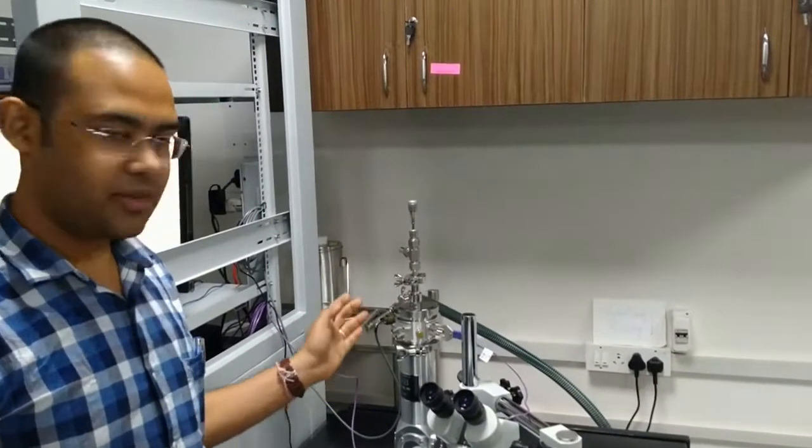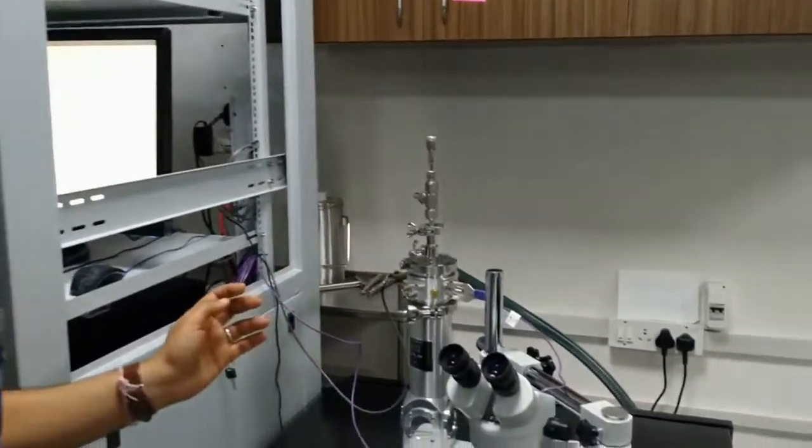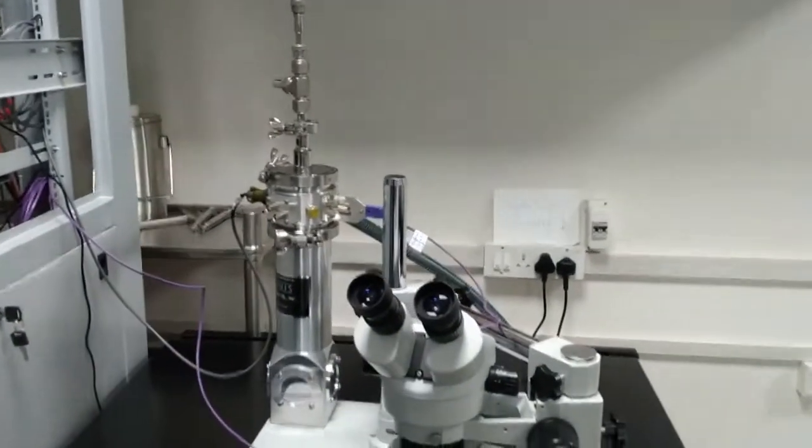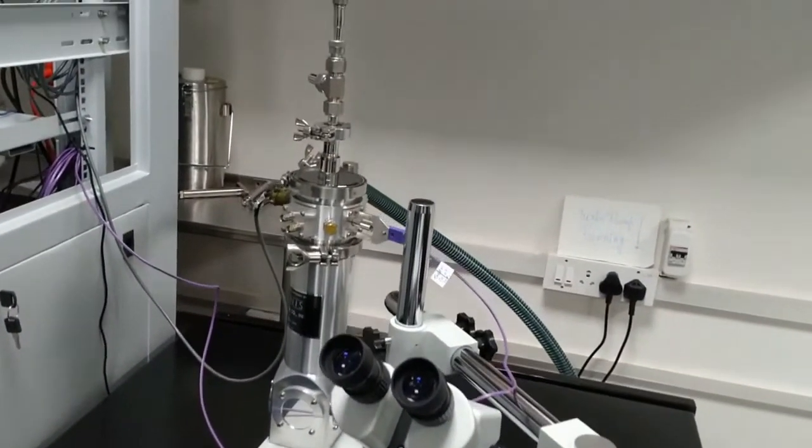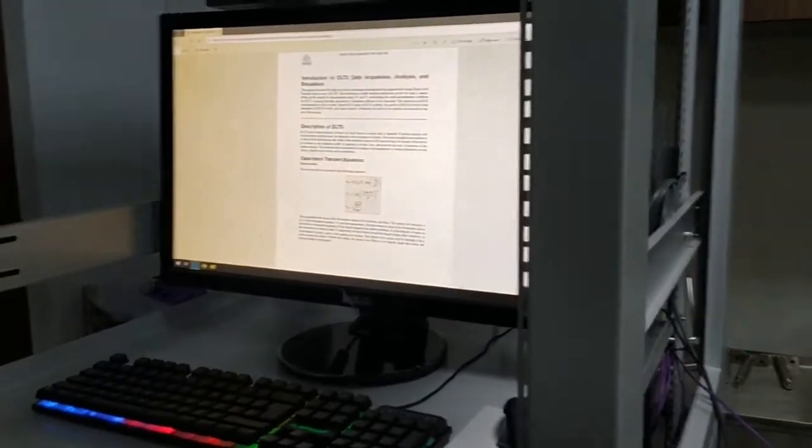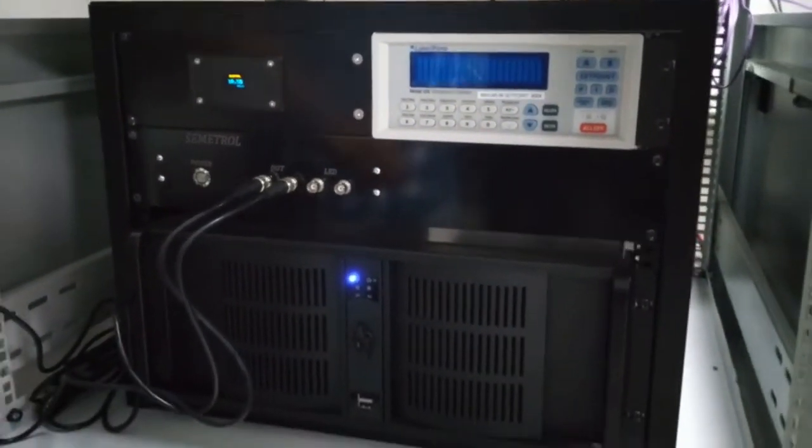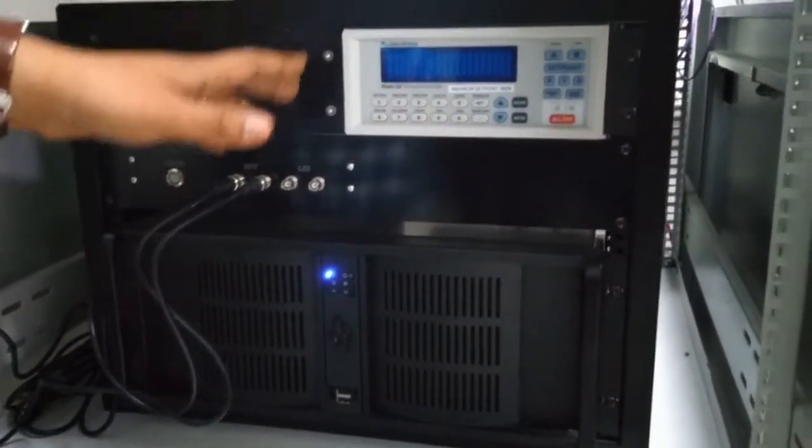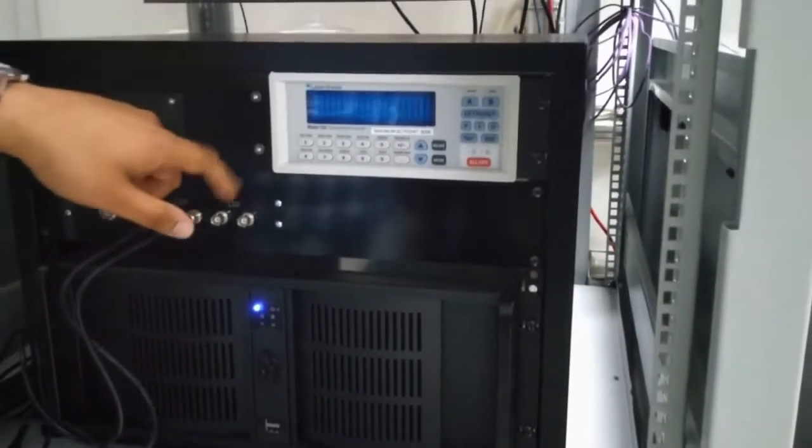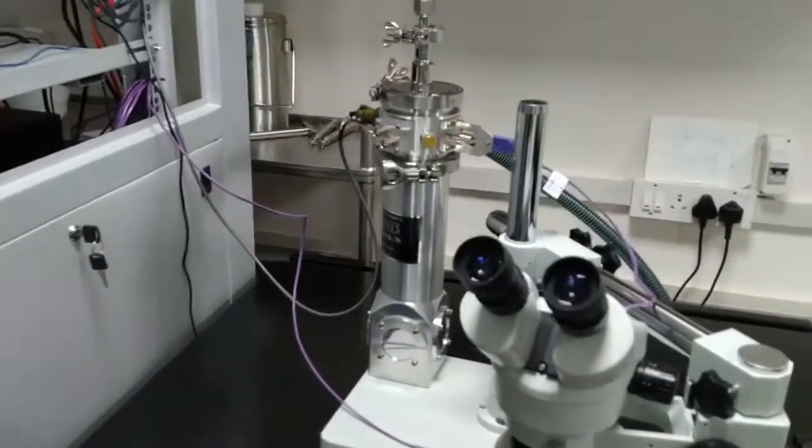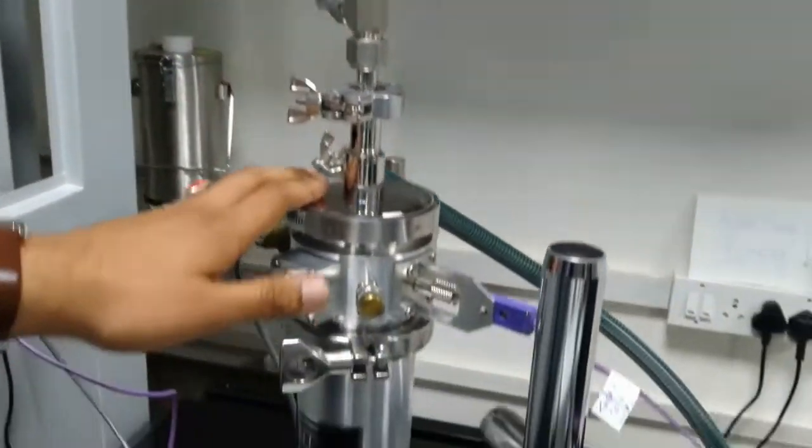This is the deep level transient spectroscopy system which is used to identify energetically deep traps which can be present in trace amounts in our semiconductors, otherwise not detected using normal IV-CV measurements. The trap detection is carried out by measuring fast capacitance and current transients in diodes and MOS capacitor-like structures under different bias conditions over a wide range of temperatures controlled using this PID controller where we can control temperature from 77 Kelvin to around 800 Kelvin. The devices are probed and loaded in a cryo chamber where vacuum of less than 10 millitorr is maintained.